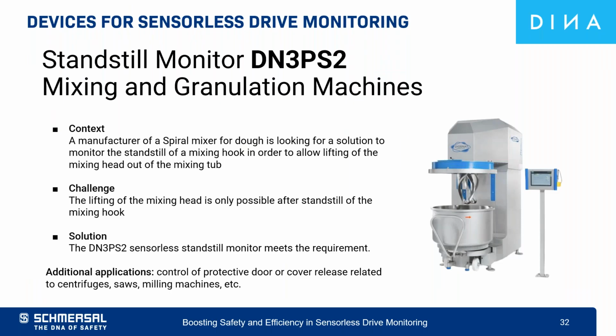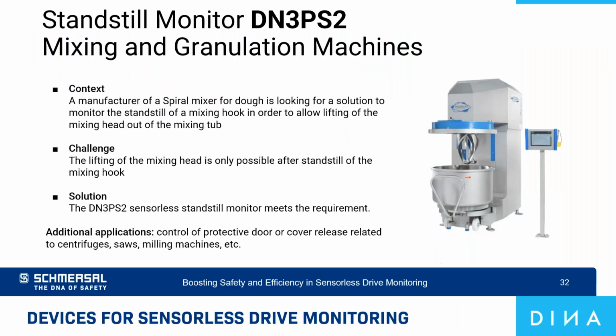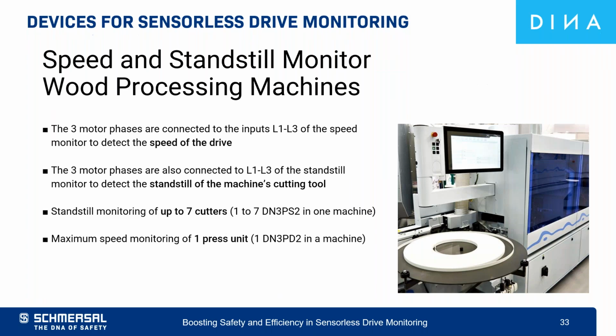In general, it can be used not only for mixers or granulation machines. You have similar challenges when it comes to milling machines, saws, centrifuges, or cutters, and many more. So, for example, on the next slide I brought you an application example where we use both the standstill monitor in combination with the speed monitor. This application example comes from the wood processing industry, and especially it's related to an edge banding machine. Here we monitor with the DN3PS2 in one machine up to 7 cutters. And in parallel, we use the DN3PD2 to monitor the maximum speed of a press unit.